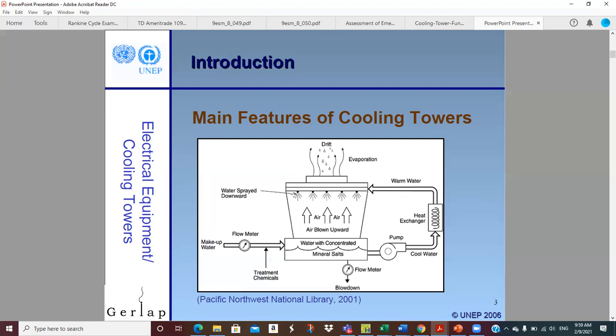Okay, so we got air coming across and up, and we got water falling down. We get this evaporation, and so water can come out of this thing. There's a couple of ways. One, evaporation. So you got molecules. Drift, because this configuration shows what we call an induced draft fan.